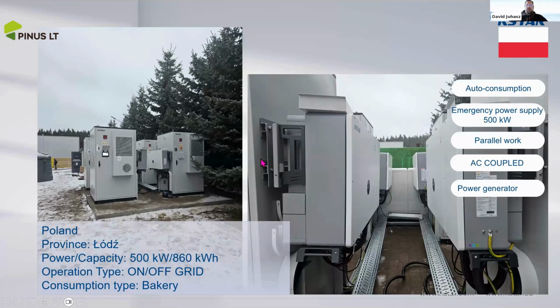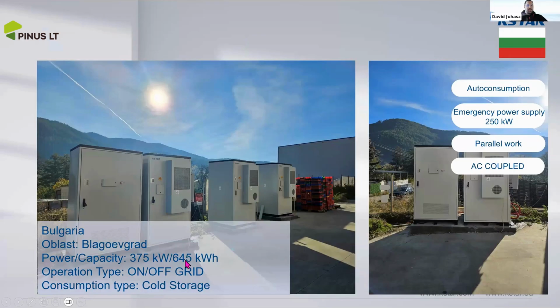Okay, the next is a bakery in another voivodeship, which decided to provide emergency supply for the entire plant, where the nominal load is about 300 kilowatts. Our approximately 500 kilowatt system can support the entire plant, supported by a diesel generator in off-grid mode. Next is in Bulgaria. It also has the self-consumption mode. It has an emergency supply, which only works after the grid has a blackout. The batteries automatically start to discharge the remaining SOC, the remaining power that we set in the minimum SOC setting.